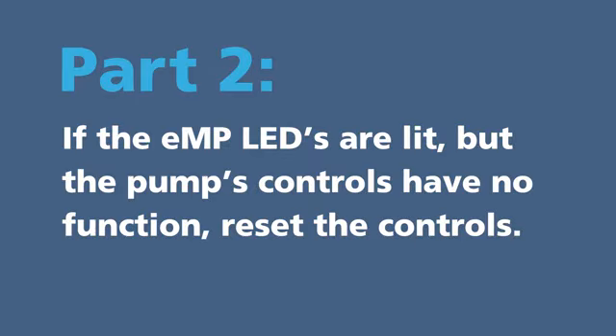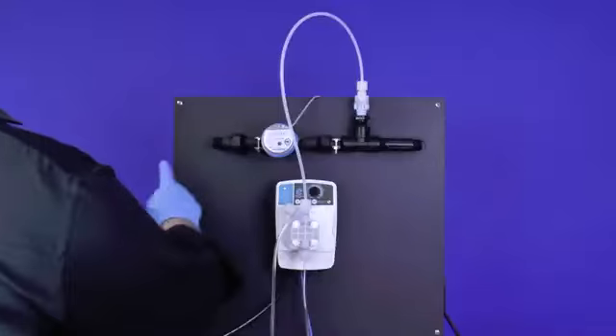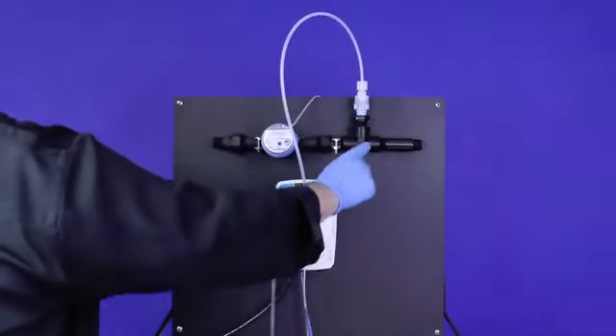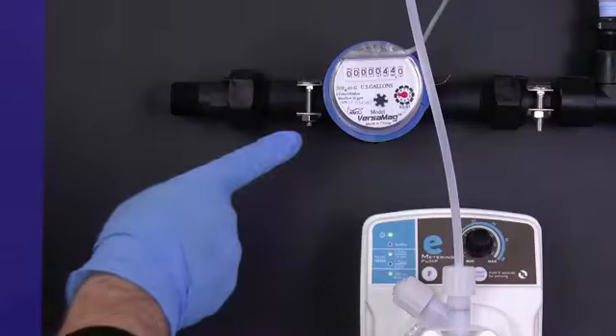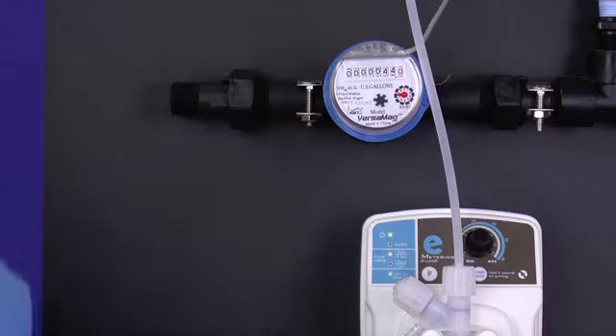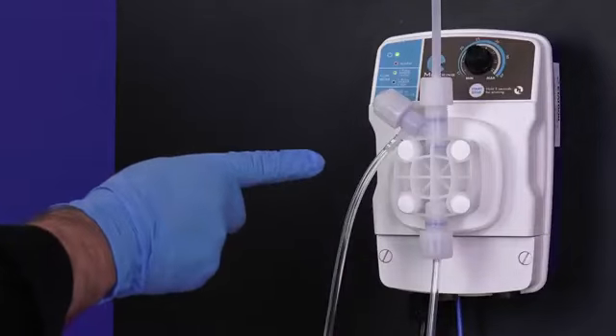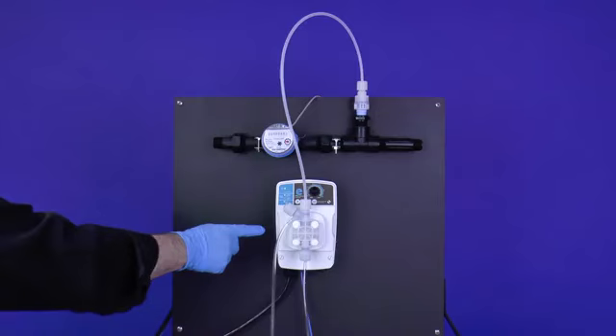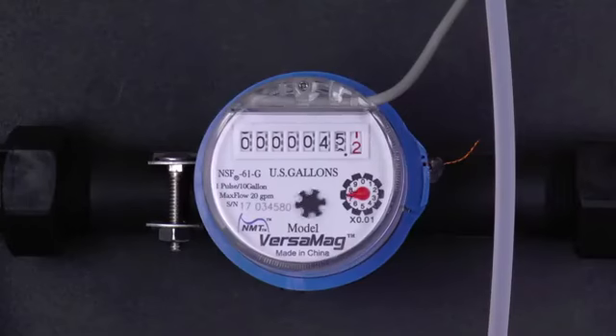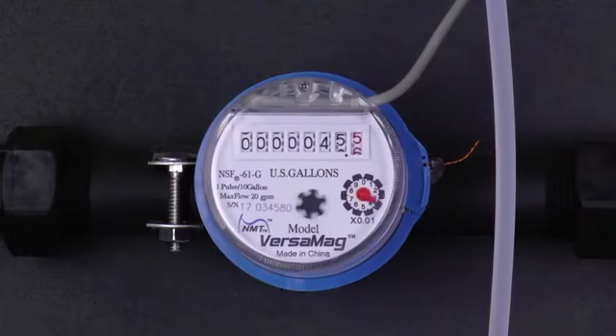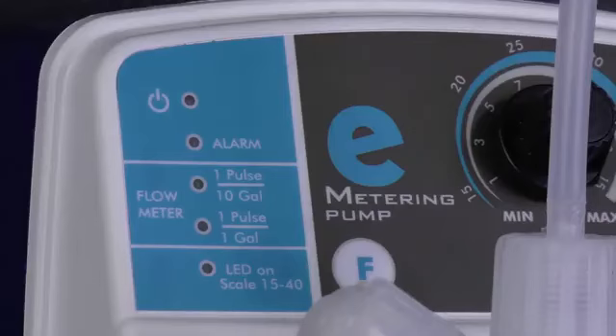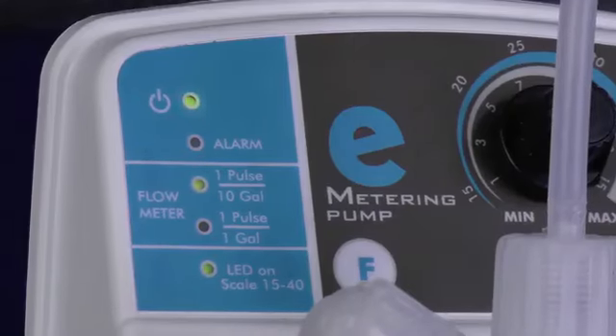Part 2. If the eMP LEDs are lit, but the pump's controls have no function, reset the controls. First, run a few gallons of fresh water through the supply line. Due to the water meter being connected to the eMP via dry contact, the water meter closes the contact to operate the pump. The running of fresh water cycles the water meter, which opens the contact. This should release the eMP controls and allows it to function properly.